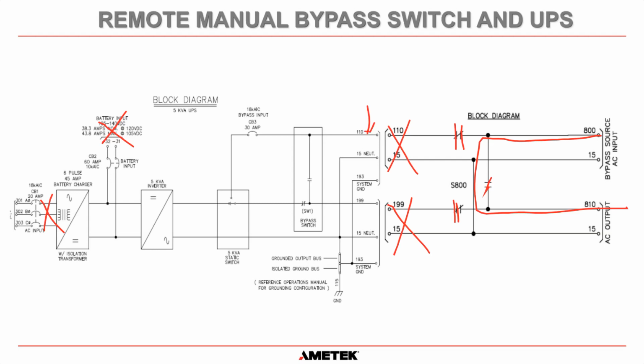we could lift that cable, we could lift that cable, we could lift the battery cables, we could lift the AC input cables and completely remove this UPS, install a new one while the load circuits are still powered up. So it gives you so much more flexibility in your plant when you have a remote manual bypass switch. Okay, so hopefully that explains a little bit more.